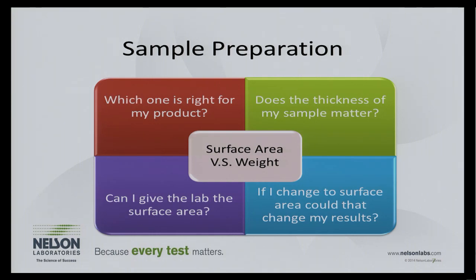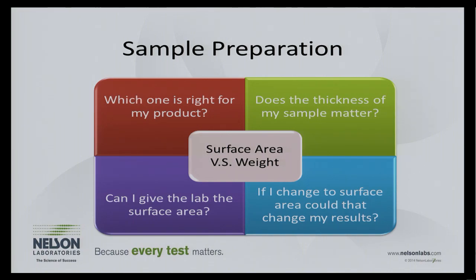Sample preparation is where everything can be variable. If you tell me you failed a test at one lab and passed at another, the first thing I'll look at is how the sample was prepared — because once we have the liquid extract, the test is pretty standard across labs. The ISO 10993 standard gives us two options for sample preparation: surface area and weight. We can use either the surface area of the patient-contacting portions or weigh the device, and that determines how much extraction volume to add.